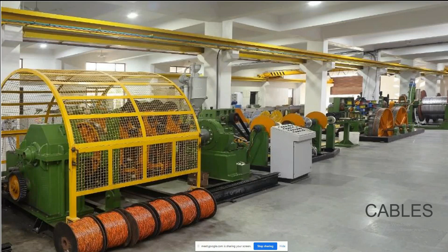Then coming to cables. In cables, we offer different insulations. These start with, I would say, the most used, PVC up to 105 degrees centigrade, XLP, ETFE, silicon, FEP, and PEEK, which we can extrude, up to 250 degrees centigrade. Teflon, PTFE, up to 260 degrees centigrade, which is wrapped and sintered, and we can also do extrusion of PFA. Polyimide can be done up to 310 degrees centigrade.